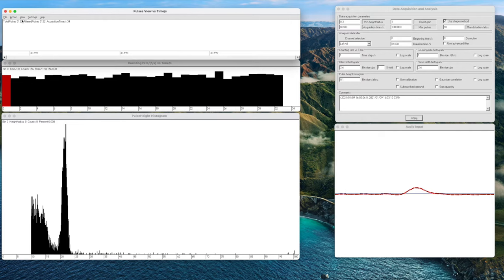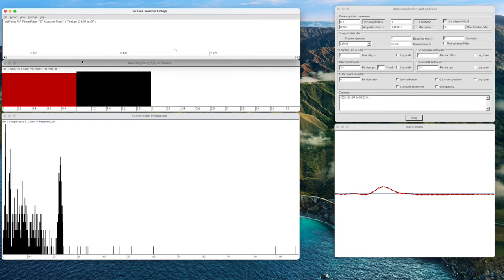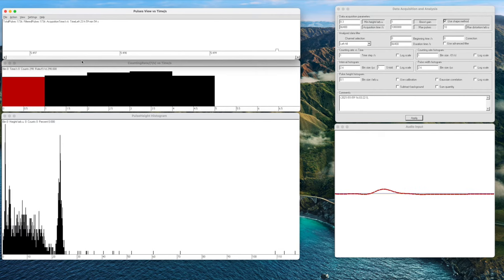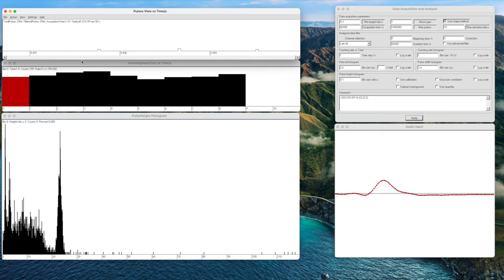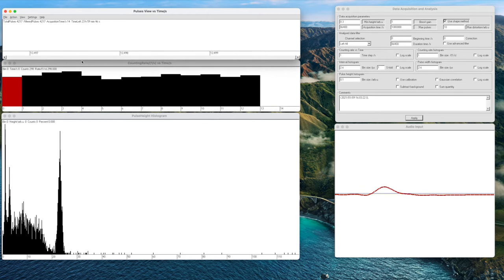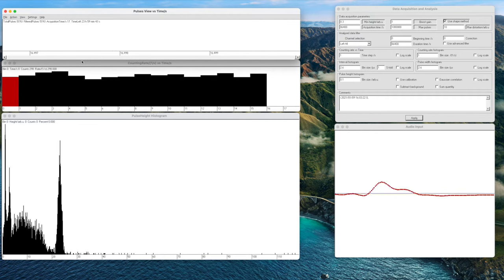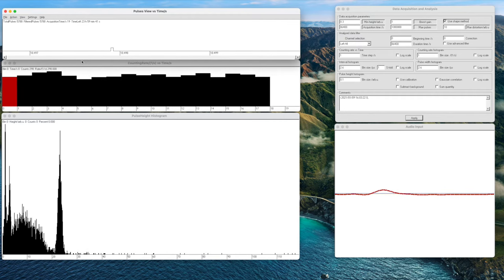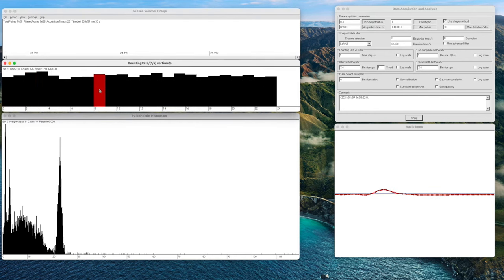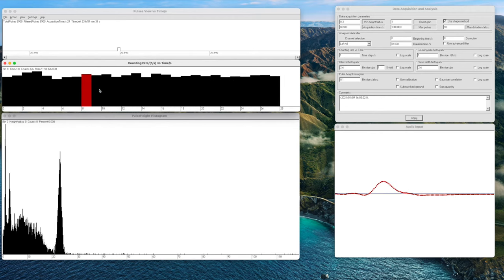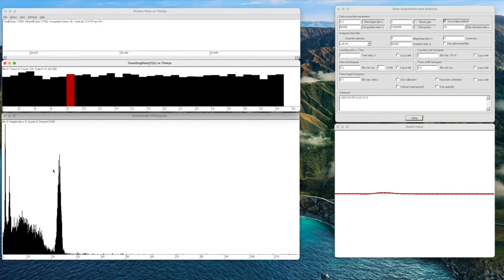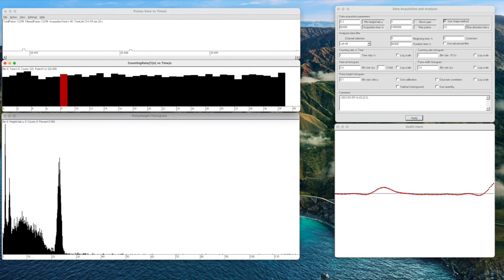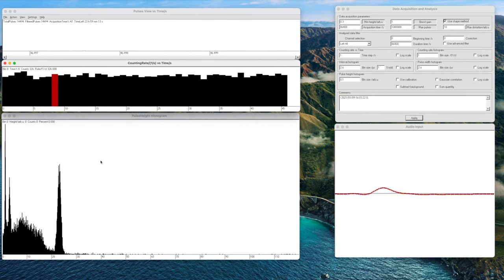Now we are ready to start our spectrum and we go to action, start data acquisition. So now we are recording a brand new spectrum and using that pulse shape to discriminate any badly formed pulses. As you can see the spectrum shows up very quickly on the screen and becomes more clear as time goes by. We see up here in the counting rate versus time window that this detector is now running at 326 counts per second which is in the low range. As you have already suspected I have placed a cesium-137 sample in front of my detector.